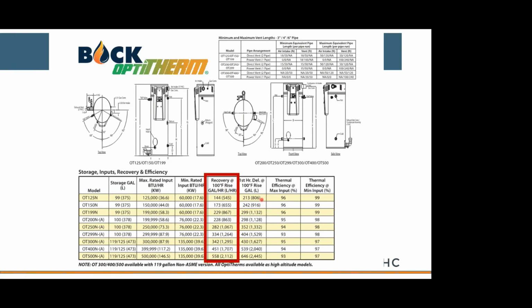The other thing to watch out for on tank type is whether you need an ASME code or not. You'll notice that the first three here don't have an A next to them, meaning they're non-code water heaters. As soon as we get into a unit that's 200,000 or greater, it's got an A next to it, indicating ASME. So if you look at typical code, ASME requirements for a water heater are anything that has a burner greater than 200,000 and storage greater than 119 gallons. So that's kind of your cutoff.